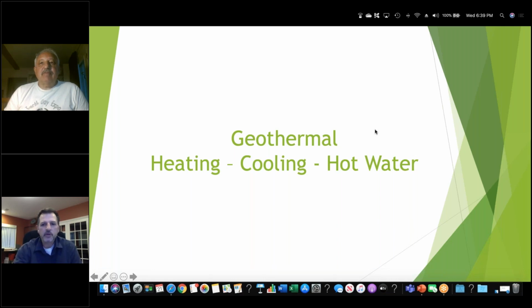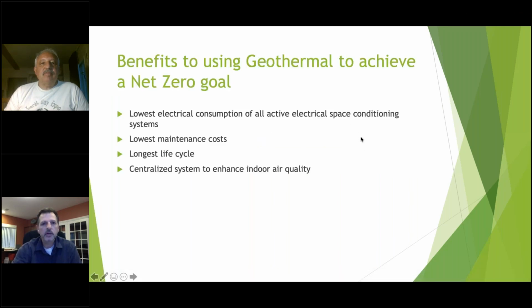So with no further ado, we'll talk about geothermal heating, cooling, and hot water and how it applies to net zero homes. First, geothermal offers the lowest electrical consumption of all the electrical space conditioning systems. John mentioned COPs and EER values; geothermal equipment has COPs approaching 4 and 5, with EER levels at 30 plus. These aren't regulated by outdoor air temperature, because geothermal systems pull heat energy from the earth, which is a stable, constant temperature, providing additional capacity and efficiency.